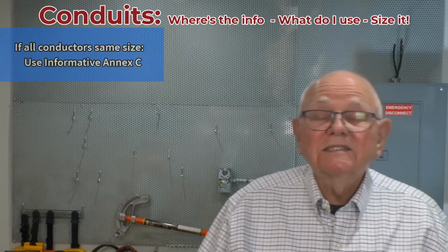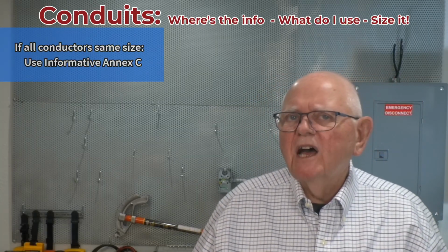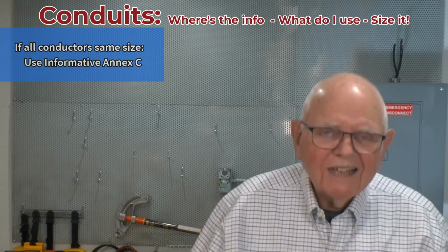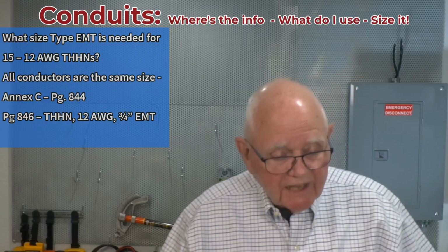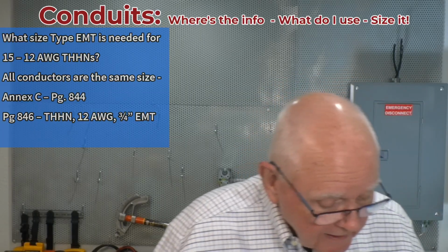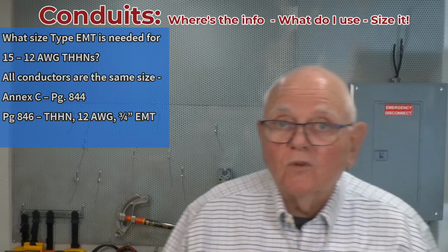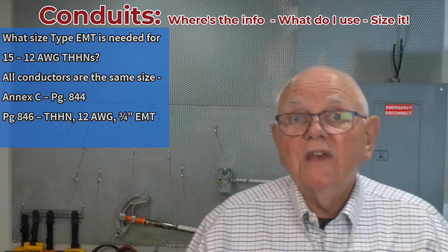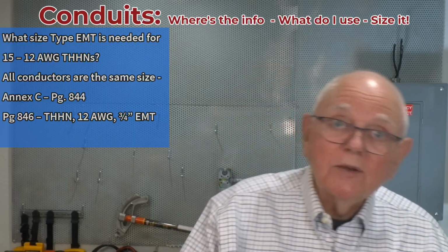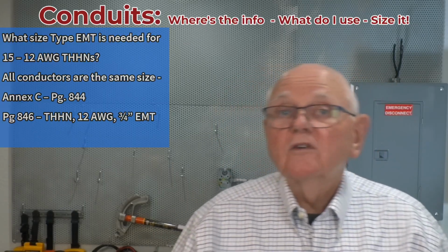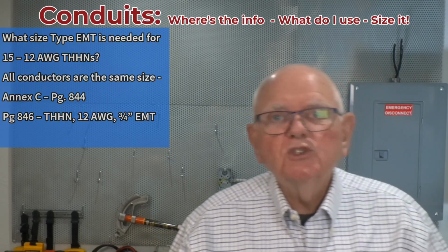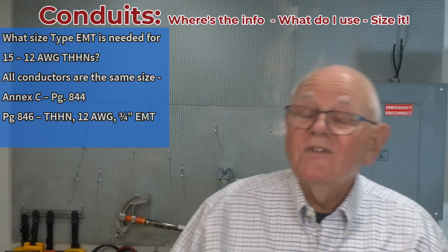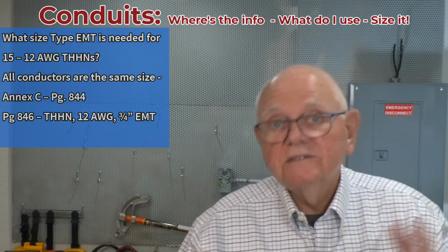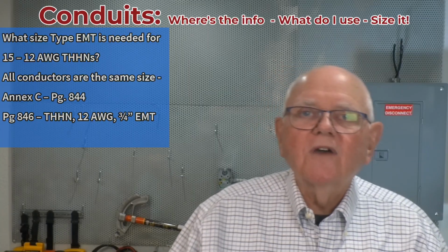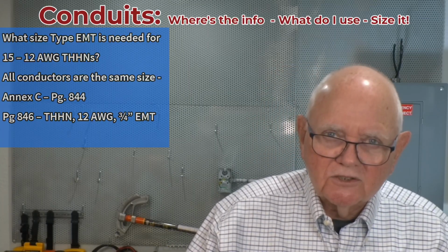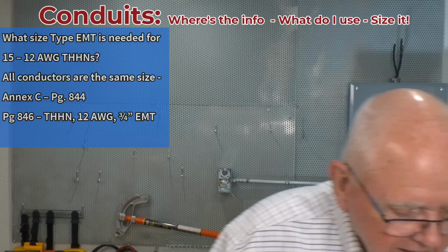So let's take a look at an example where all my conductors are the same size, and I need to determine what size conduit I need. In this example, let's say, I don't know. I'm going to start, by the way, on page 844, where I find Informative Annex C, and you're going to find the table of contents for Annex C on page 844. You'll notice that there is a table for each one of the different types of conduits. In fact, there are 2 tables. There's one table for the conduits and another one if I'm using compact stranded conductors. That's the table that's designated as A.